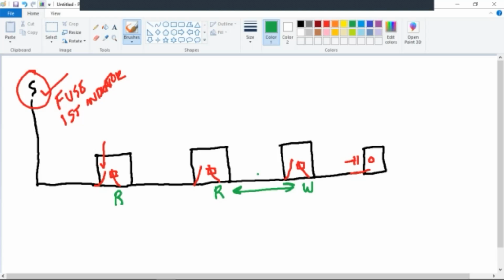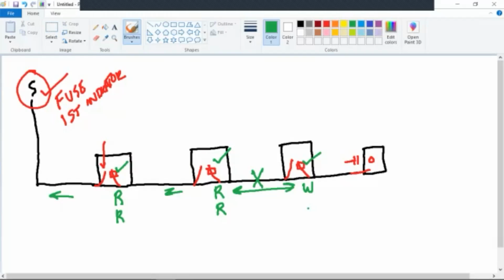All right, say the fault occurs right here, okay? It's returning, remember, neutral's back this way. This is where we're grounded at, all the way back through the back of the line. Did fault current go through this indicator? Fault is here. Yes. That's why it's turned red. Did fault current go through this indicator? Yes, that's why it's red. Did fault current go through this indicator? No, because the fault happened prior to it. That's why it's white. Okay. Fault is between red and white indicators.